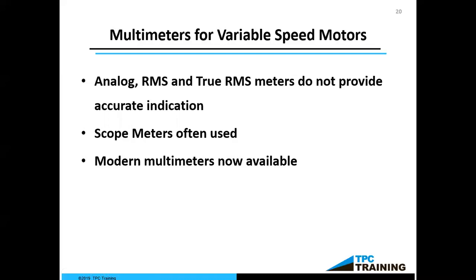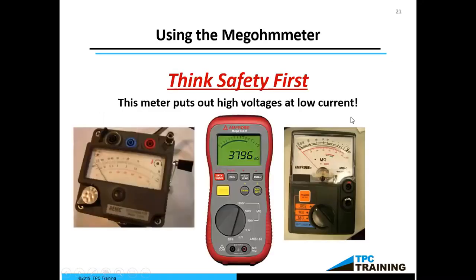The meters that are nice to use are these true RMS meters. And so a true RMS meter really gives me a good look at the sine wave. If I do have a meter that does have an oscilloscope on it and I can actually see the sine wave, that's great. And if your motor is connected to a VFD, and you have a meter that has an oscilloscope on it, you can determine if that sine wave has been distorted or not. And that's a very valuable tool. So the better meter we have, the better we can do diagnosing our situation.